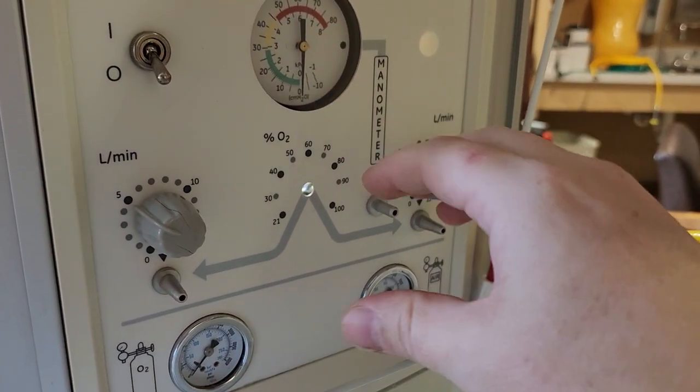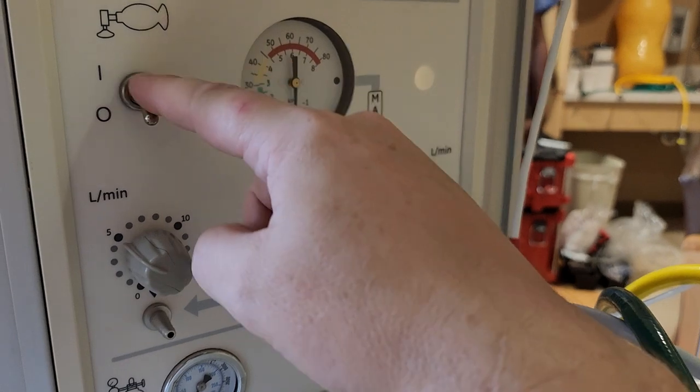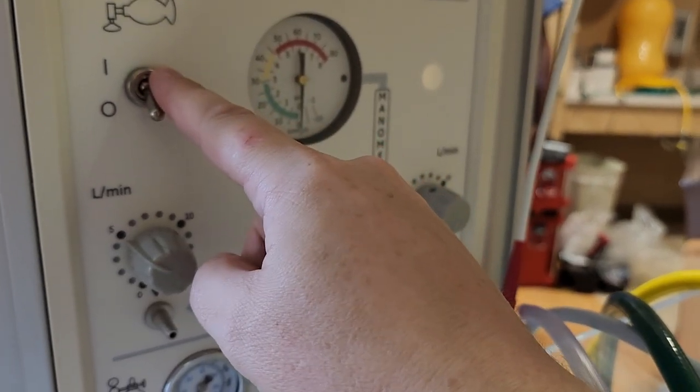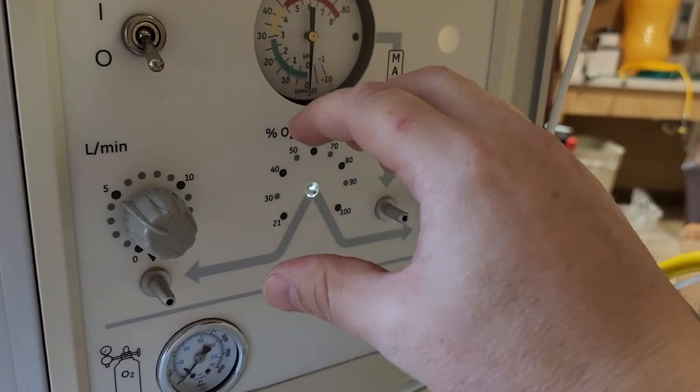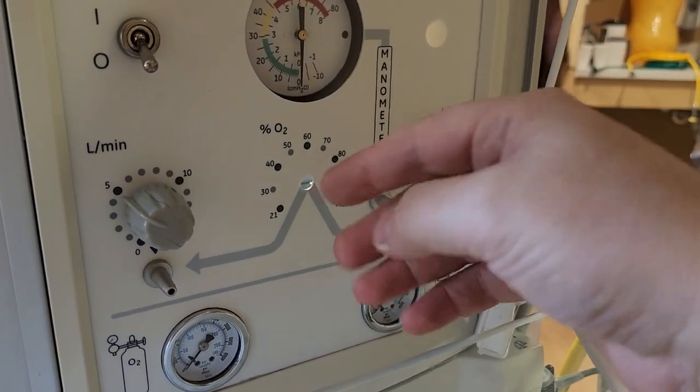So I'll show you how I can prove that. What it's doing is because there's bypass going on the switch, it's contaminating your med air with oxygen so you're not getting the correct percentages that you would normally be expecting.